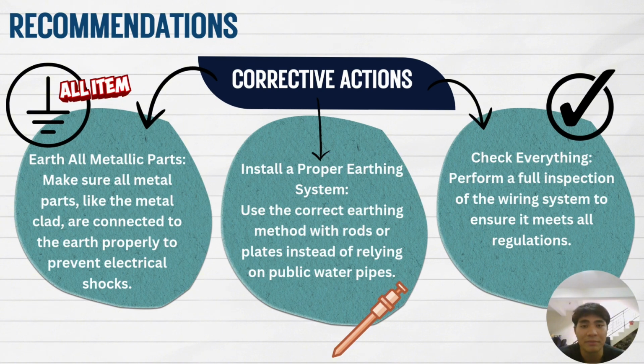First, all the metal parts, like the metal clad, must be properly connected to earth. This will make the system safer and prevent electrical shocks. Second, a proper earthing system needs to be installed; we must use a rod or plate instead of just a water pipe, which is not safe and breaks the law. Finally, we should do a full check of the wiring to make sure everything follows the Electricity Regulation 1994.